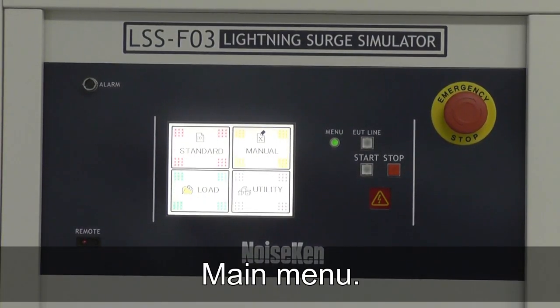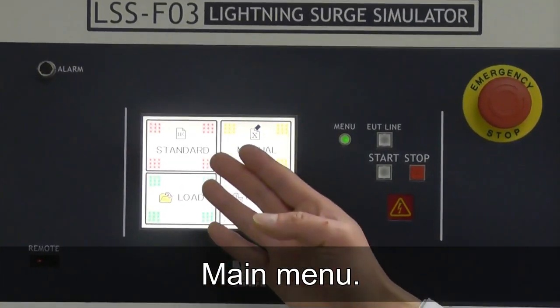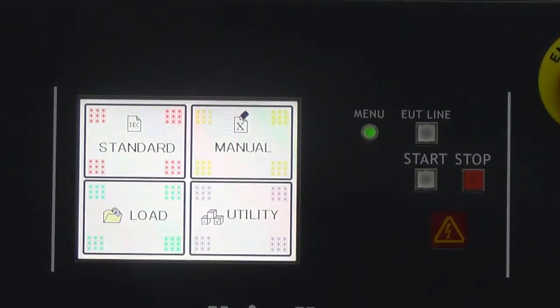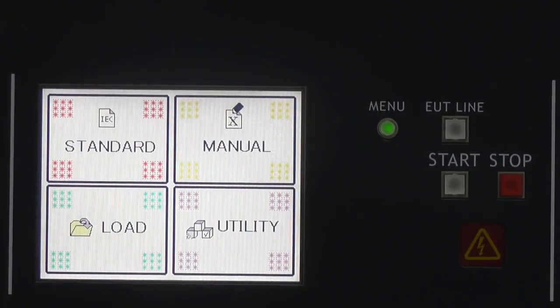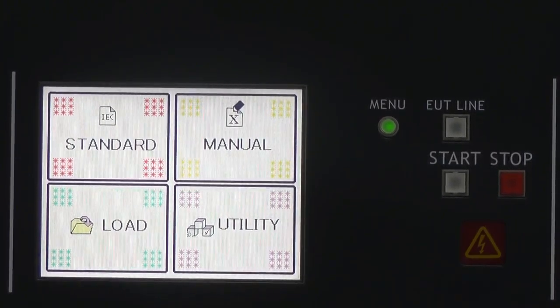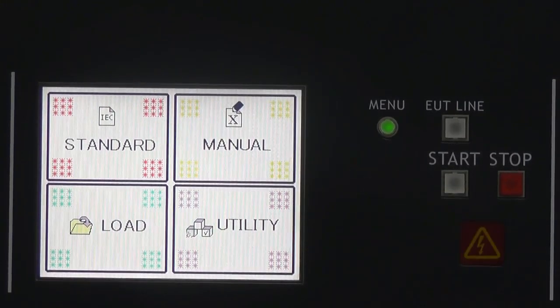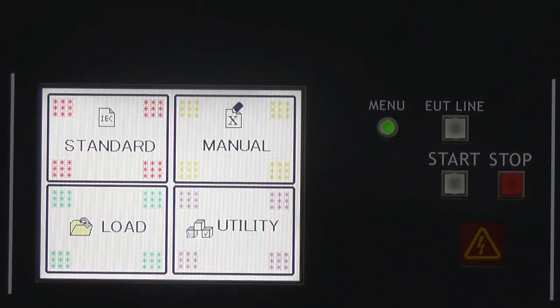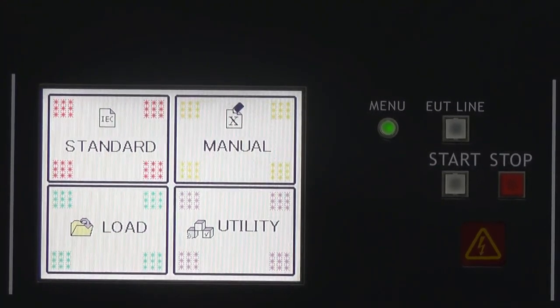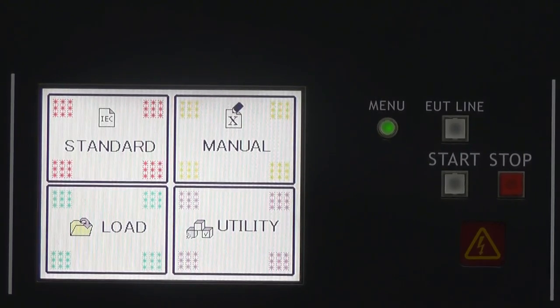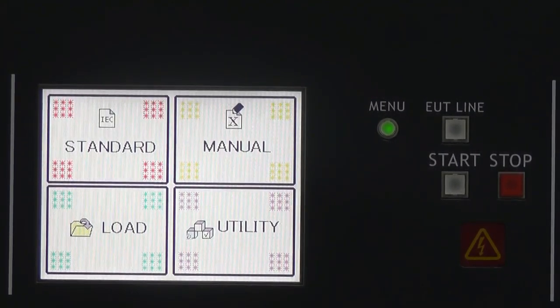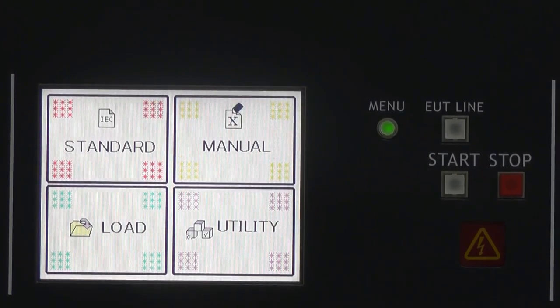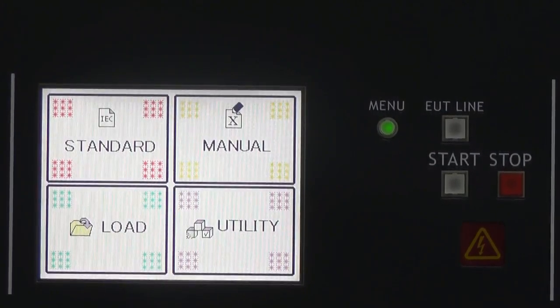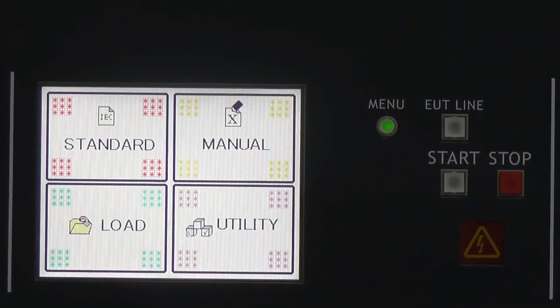Well, this is the main menu. There are 4 menus here. In the standard menu, the settings specified in the IEC 61000-4-5 are preset. And it is the mode that offers to start the test with minimal operations. In the manual menu, this mode is used to perform non-standard tests. Various settings as well as the sweep testing are available, and you can also save the settings and recall them to quickly start the test next time. In the load menu, you can load the settings saved in the manual test. In the utility menu, you can set the protection of the test settings and the operation when using specific functions.